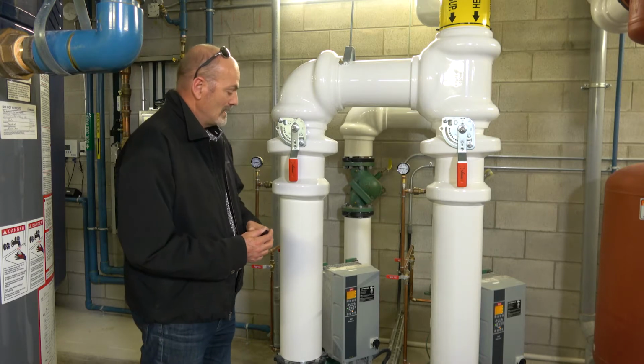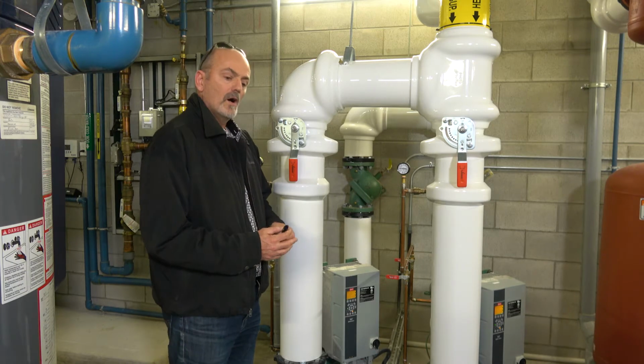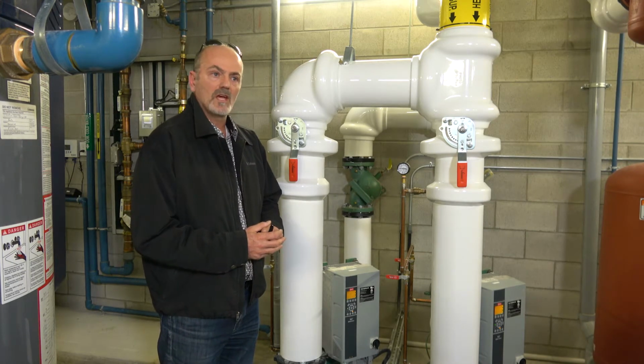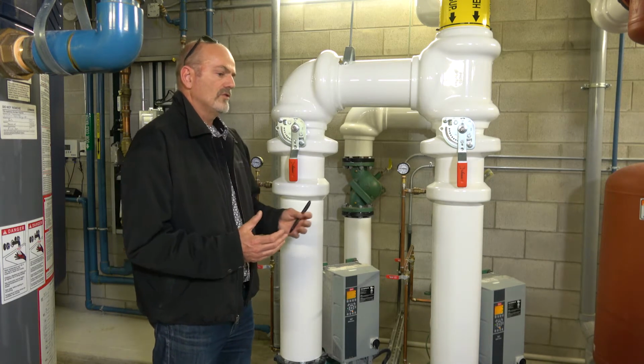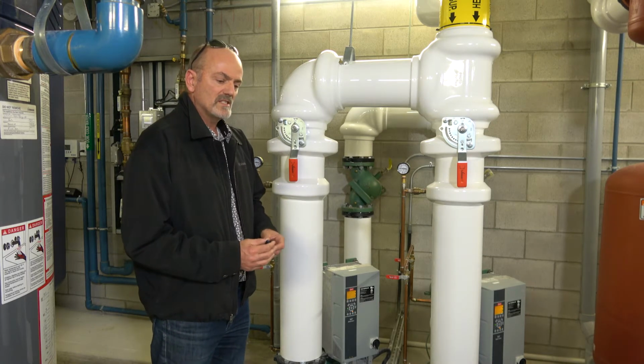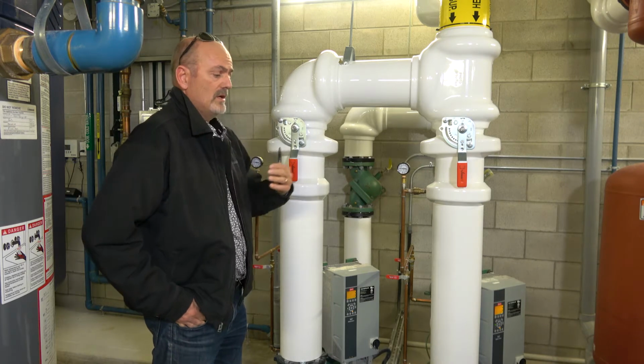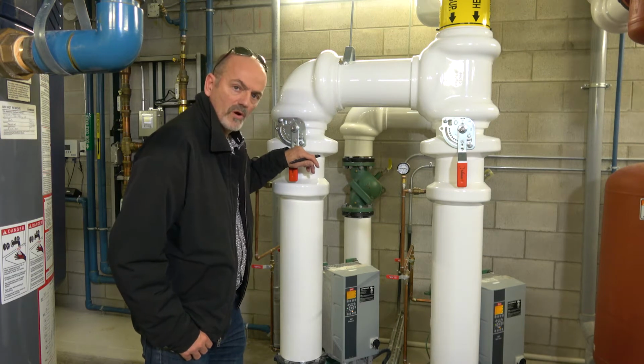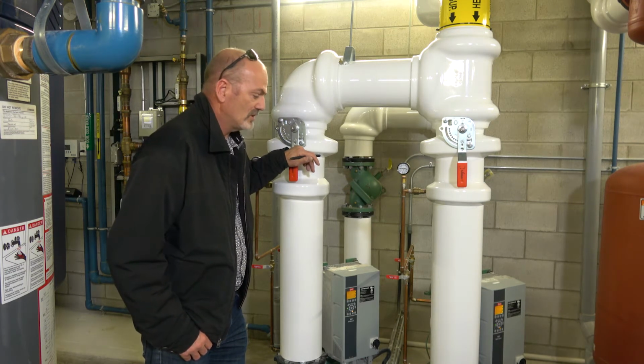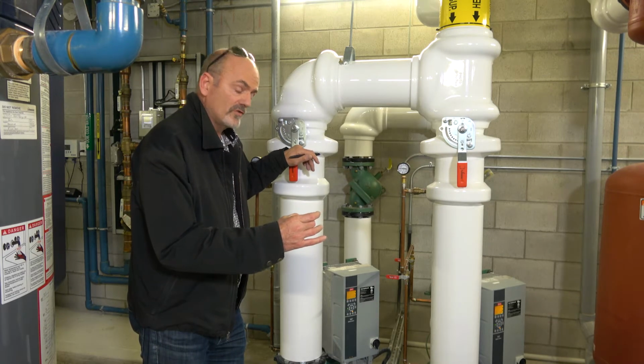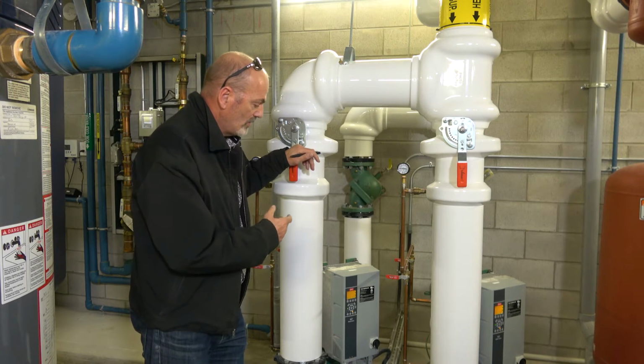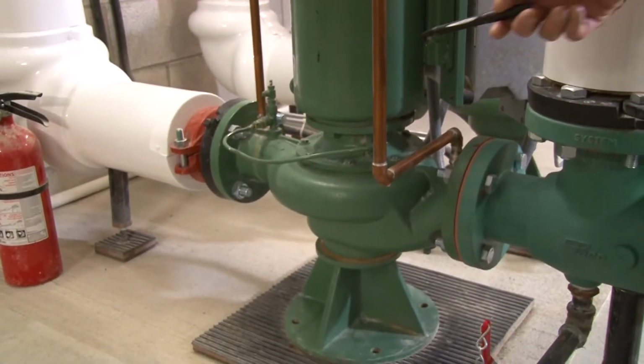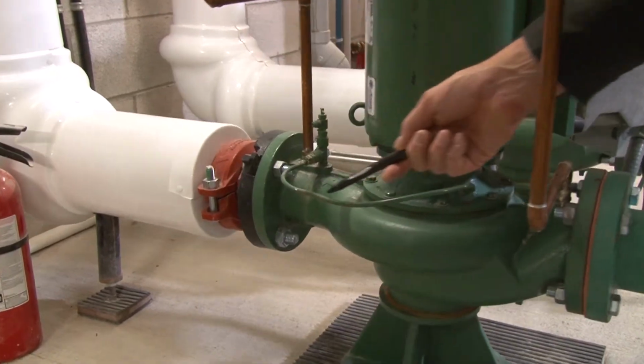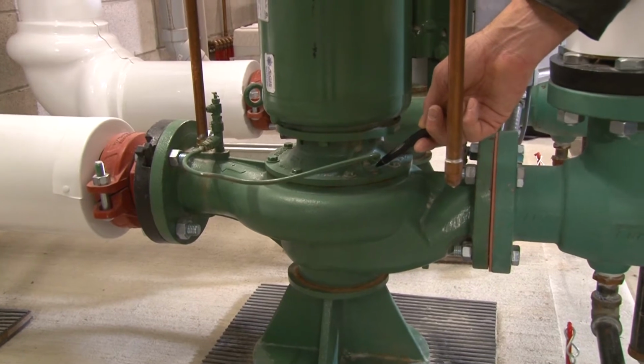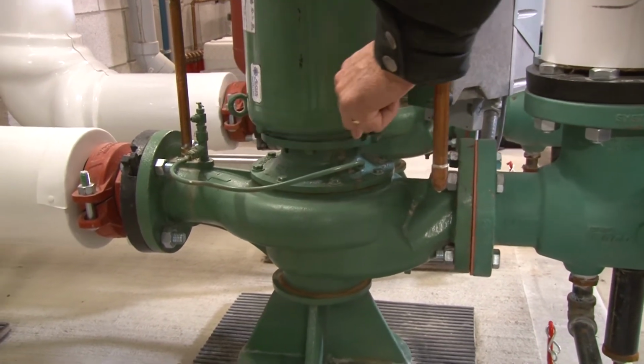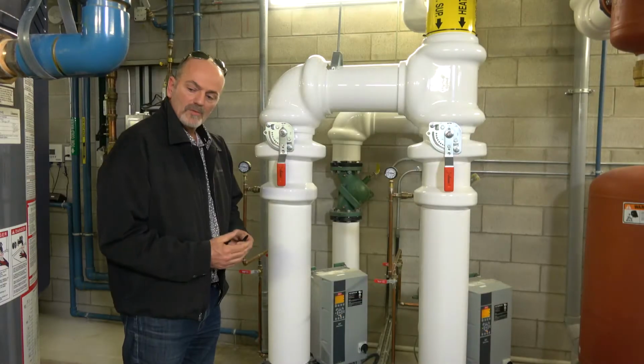What can happen over time is that the seal can wear. It's dependent on the ongoing maintenance and chemical treatment of the fluid in the system. The initial seal leak can be premature, or it can be way down the road. It depends on how much debris in the piping, during the cleaning and flushing process, got across and between the two seal surfaces. Because the seal surfaces are constantly flushed with a seal flush line, which I don't know if you can see, between the discharge side of the pump there's a small seal flush line that goes into the pump cover, and it allows a small amount of fluid to be constantly flushed across the seal surfaces. And that helps get any debris off the seal faces.